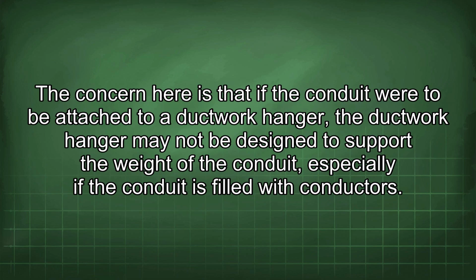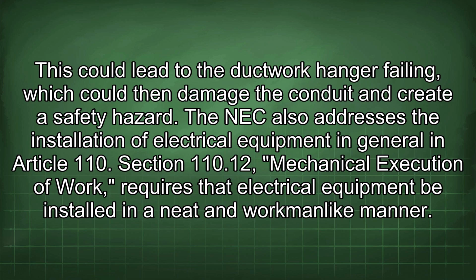The concern here is that if the conduit were to be attached to a ductwork hanger, the ductwork hanger may not be designed to support the weight of the conduit, especially if the conduit is filled with conductors. This could lead to the ductwork hanger failing, which could then damage the conduit and create a safety hazard.